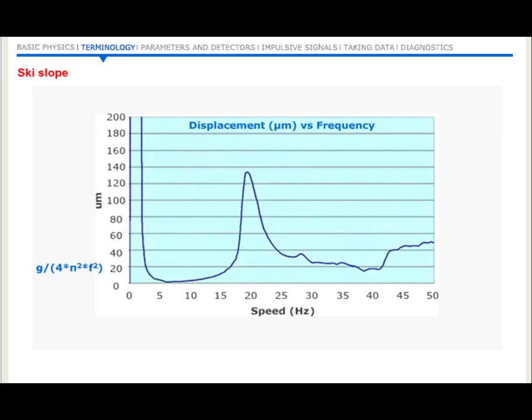Causes of low-frequency signals in the vibration spectrum are: A. It is a real signal, that is, low-frequency vibration is actually present. B. It is a false signal caused by instrumentation faults, for example, poor screening, poor contacts, incorrect selection of an appropriate transducer. C. Electrical noise generated by the sensor's inbuilt electronics. This is sometimes referred to as ICP noise. ICP stands for Integrated Circuit Piezoelectric Sensor. Item C is the most common.